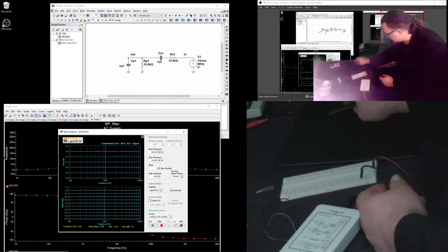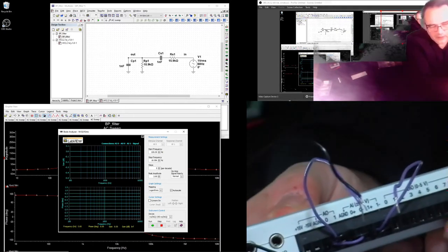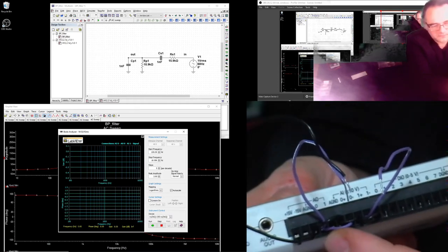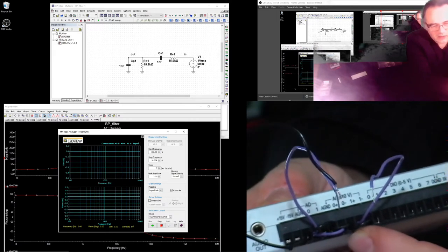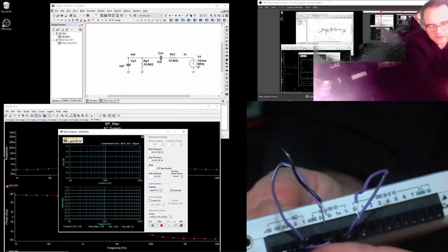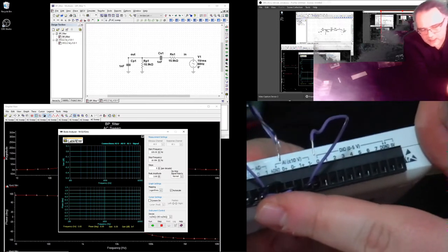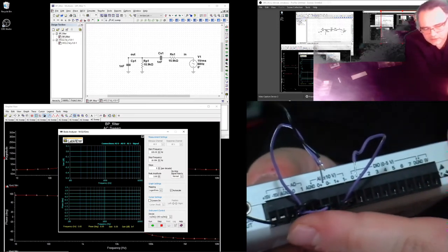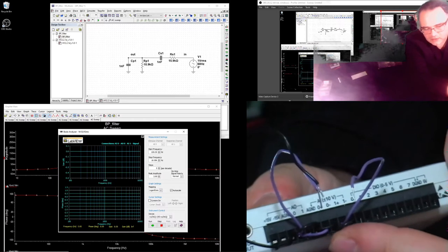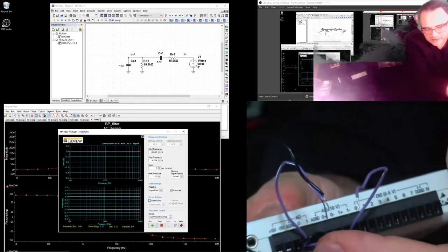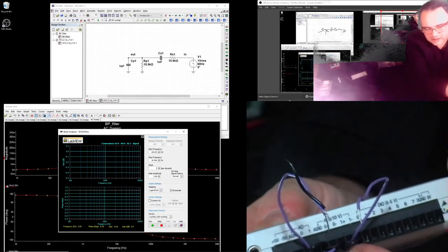I can show you now what this means. Here are the inputs. So this here is the analog input AI 1 and 0, and you see that it's differential. While here is the analog output AO 0, and it has two ports, 0 and 1. Now the problem is that analog inputs 0 and 1 are differential. You see that there you have 0 plus, 0 minus and 1 plus and 1 minus. Well, I want to measure single-ended.